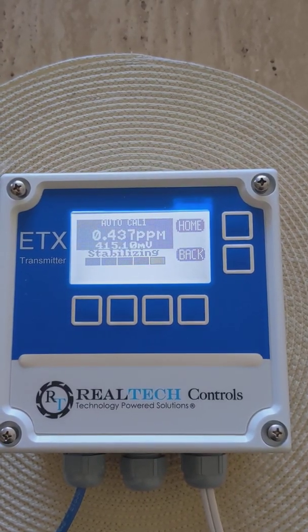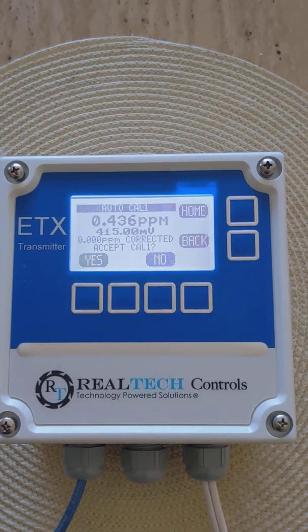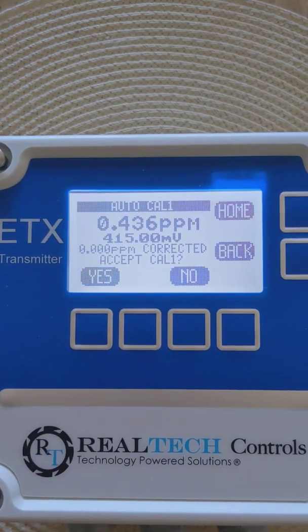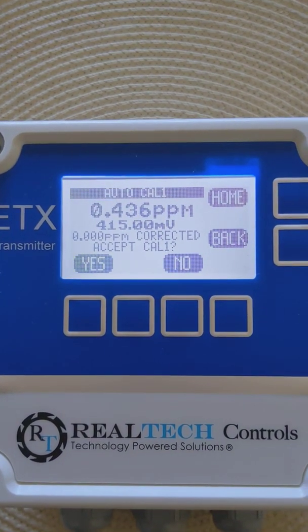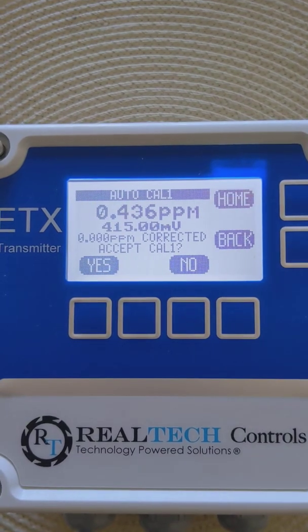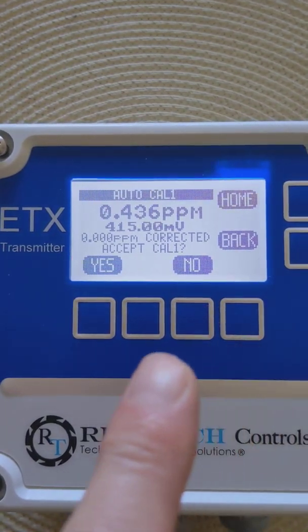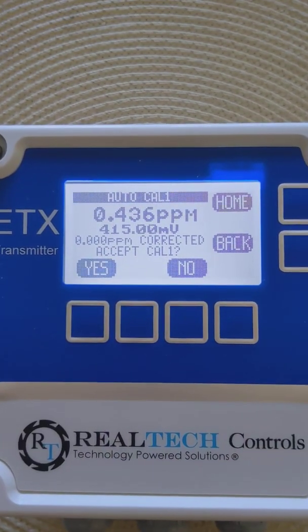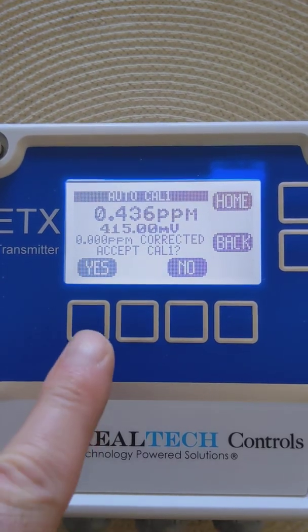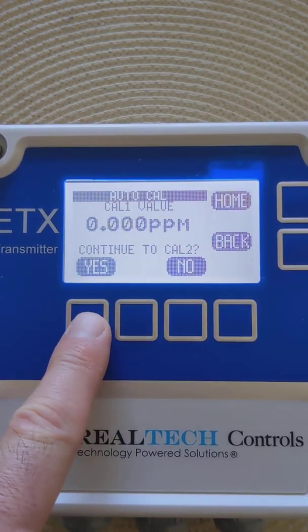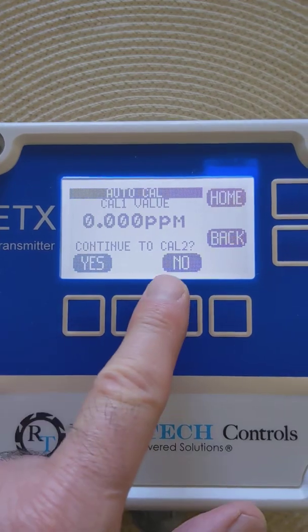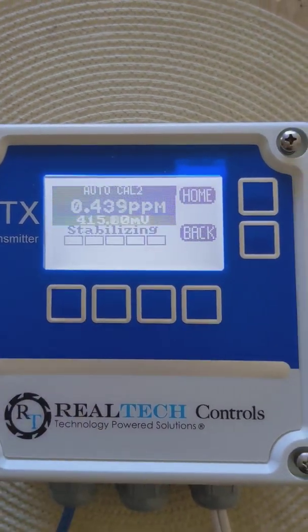Then when all the bars are complete, it'll give you a value. It'll say accept 0 ppm. If that is not the correct one, you can always choose no and go and enter in a value. But for all intents and purposes, I'll say, yep, that's correct. Accept 0 ppm for that. Continue to calibration 2, push yes.